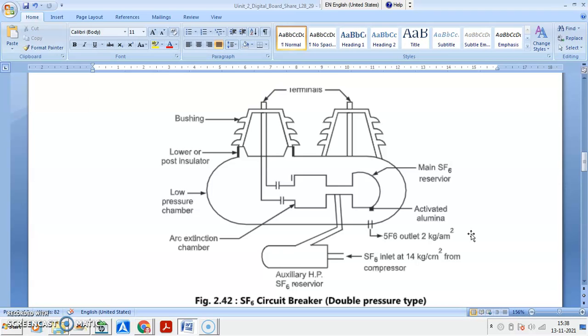Then you are having storage, low pressure chamber, high pressure chamber gas, for which you have to provide all electrical safety to the tank. Then third is the arc extinction chamber. You are having the arc extinction chamber, which is supported by insulating material. The arc extinction process takes place inside the chamber, and you are applying the high pressure SF6 gas for extinction of arc.